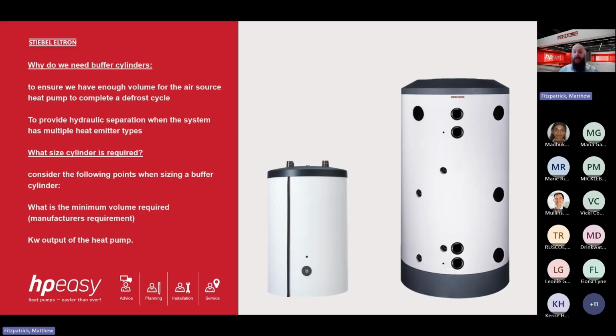And second of all, it's the kilowatt output of the heat pump. Now, the greater the kilowatts output, the larger the flow rate. So we have a large volume of water passing through. And the example I always use, we have an 87 kilowatt ground source heat pump, very commercial heat pump. And that will deliver 89 kilowatts at a flow rate of around 259 litres per minute.